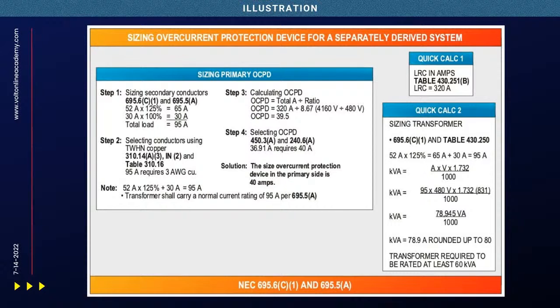Right. Now, when you look at sizing the primary overcurrent device there in step one, we're going to do the conductors first. And what you're going to notice here is I'm still doing the same calculation. You got the one motor there, you take it 125%, gives me 65 amps. Then I have my other loads at 30 amps. Add that together, gives you 95 amps. And naturally, the next size above that's 100 amps, which is a number 3 conductor. And right below that in the note, we tell you the transformer has to be able to carry that normal current rating of 95 amps.